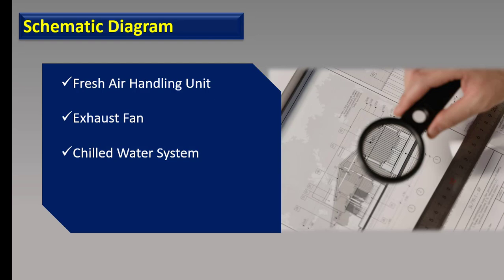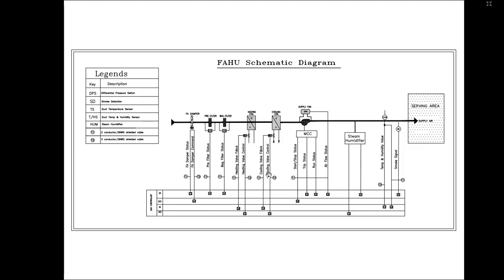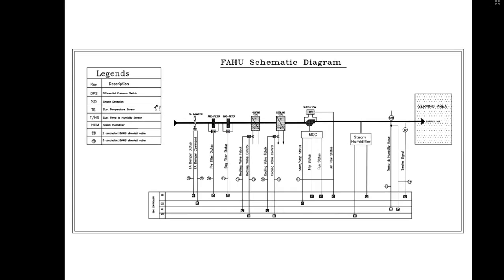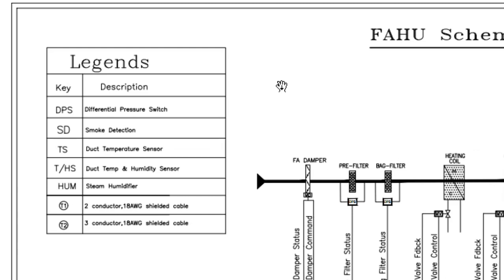I talked about all these systems in my previous videos, so you can have a look at those for more information. Here we have a schematic diagram of a fresh air handling unit or FAHU. On the left side, we have legends for this schematic diagram, where DPS stands for differential pressure switch, SD is for smoke detector, TS is temperature sensor, T/HS is duct temperature and humidity sensor, and HUM is steam humidifier. For cables, T1 is a two-conductor 18 AWG shielded cable, and T2 is a three-conductor 18 AWG shielded cable.